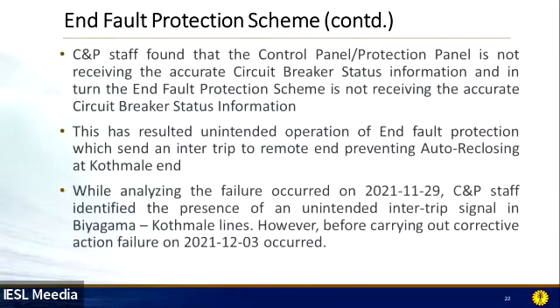While analyzing the failure that occurred on 2021-11-29, control and protection staff identified the presence of an unintended intertrip signal in the Biyagama-Kothmale lines. However, before carrying out the corrective action, the failure on 2021-12-03 occurred. So what we say here is that on the 29th incident as well, this end fault protection intertrip happened, but we could not analyze it and carry out corrective measures before the third failure.